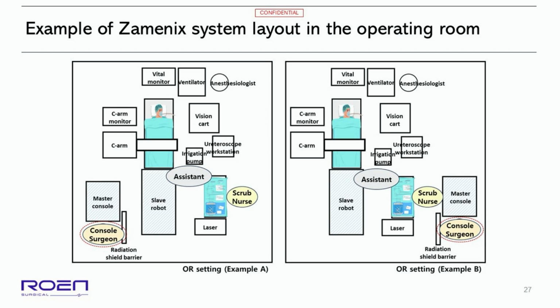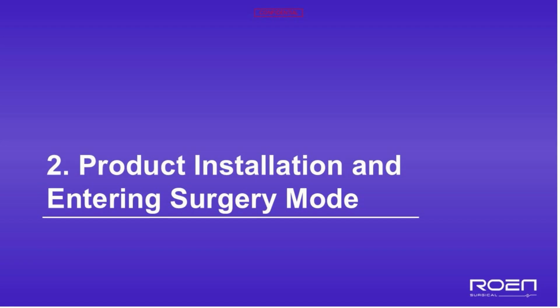Here is an example of the Zamenix P system arrangement during surgery. The slave robot should be aligned as straight as possible with the patient. The endoscopic imaging equipment and laser equipment should be positioned close to the slave robot, while the master console can be placed in a corner that does not obstruct any movement or path of either people or equipment in the operating room. Chapter 2 of the Zamenix P user training program is about product installation and entering operation mode.